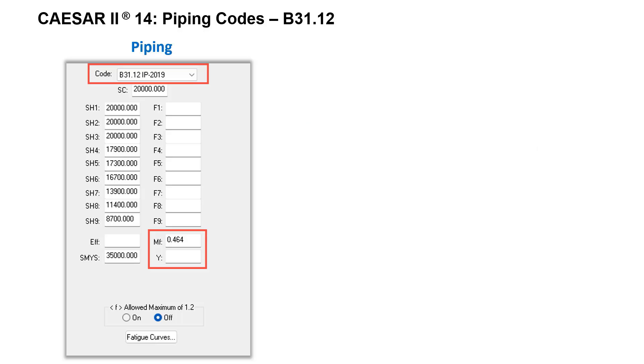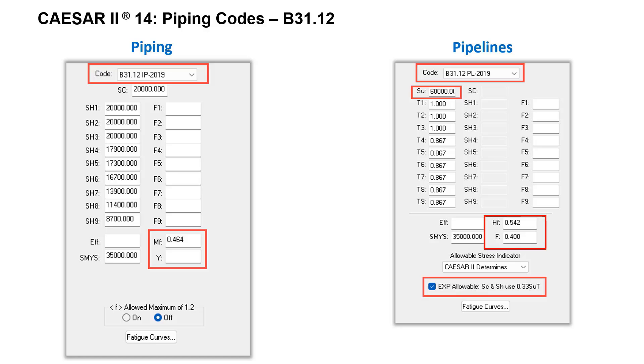The IP allowable auxiliary dialogue contains matching inputs from B31.3. Differences include new requirements for entering material performance factor MF and the coefficient Y. The PL part distinguishes between restrained and unrestrained piping in stress calculations, and uses HF material factor and F design factor.